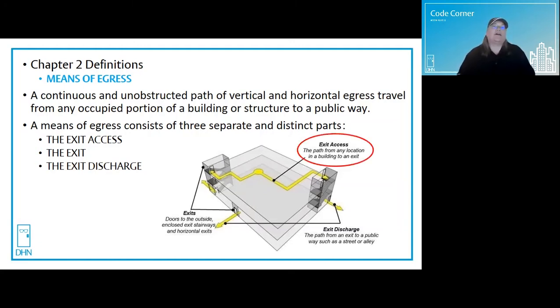The exit access, that part which leads to an exit. The exit itself, which can be either vertical, the stairs, or horizontal. And it includes exit doors and the exit discharge, which gets you out of the building to safety to the public way. Let's break them down.